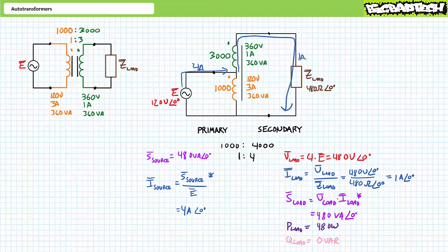An application of Kirchhoff's current law at the middle tap demonstrates 4 amps of current enters and 1 amp travels through the load, meaning 3 amps travels through the bottom winding. What you achieve in the step-up configuration is two loops of clockwise traveling current, where 1 amp travels one loop and 3 amps travels the other, such that the low voltage, high current primary experiences both current paths, whereas the high voltage, low current secondary experiences only one.